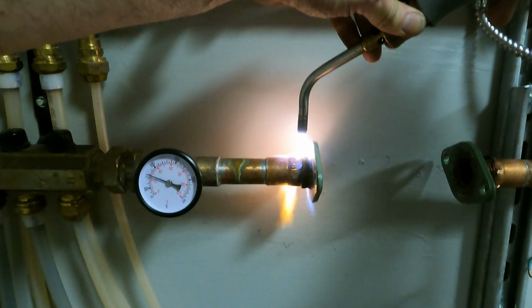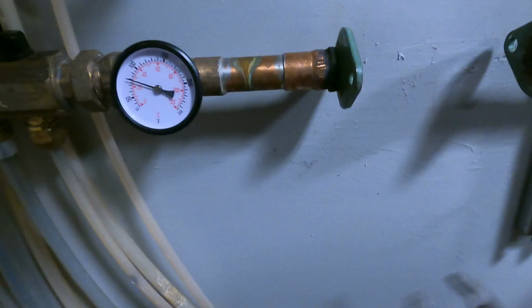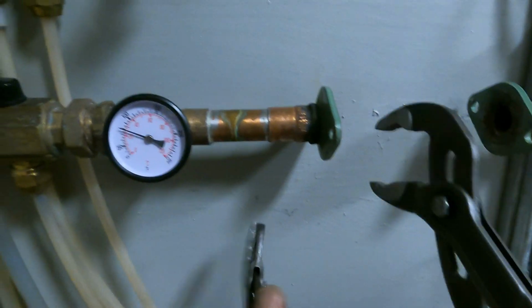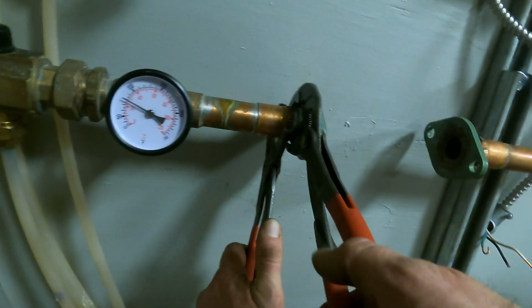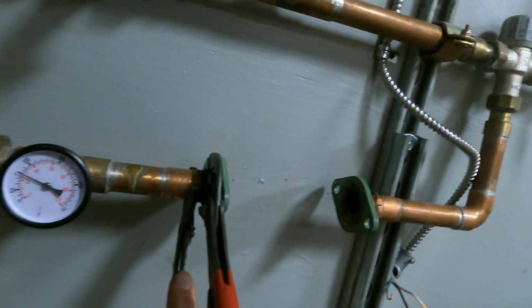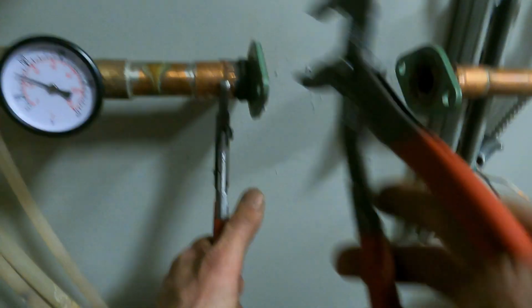How's upstairs going? Oh yeah? It's like a couple of stuck valves. The actuators are working, it seems like, but the valves, the pin is pushed all the way down and won't come back up. Even if you spray it? Yeah, I sprayed it. I even wiggled it up and down to see if it'll free it up. And you can't grab it? Yeah, it's just stuck.